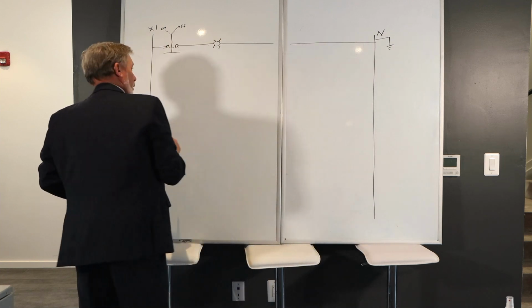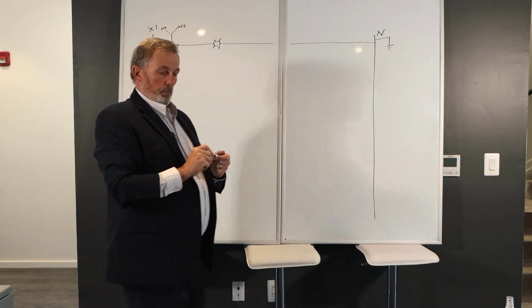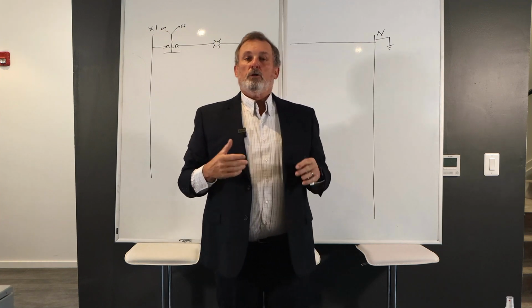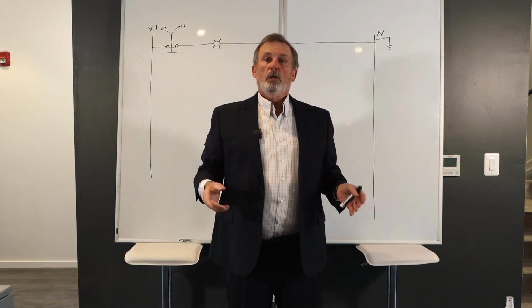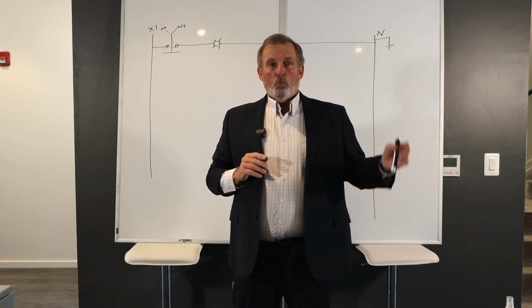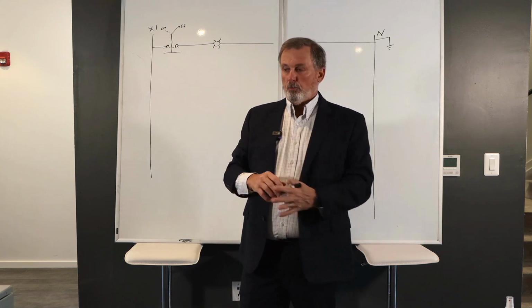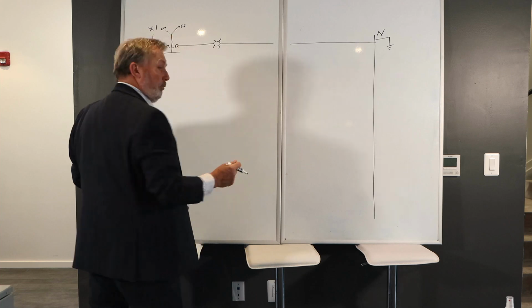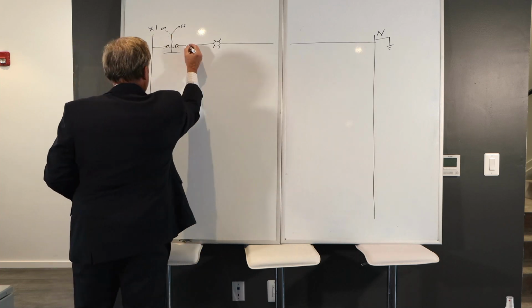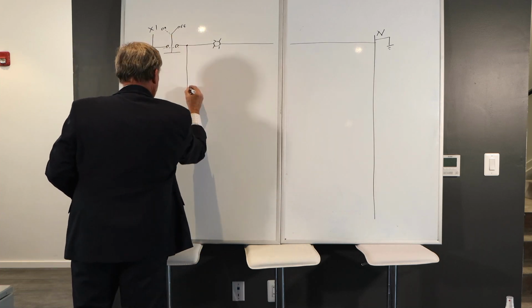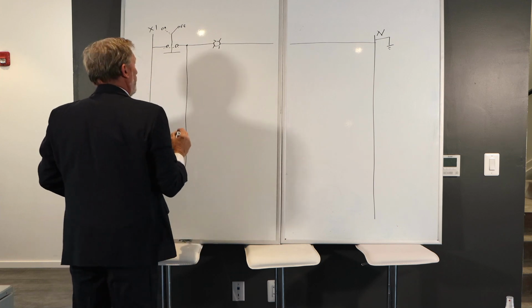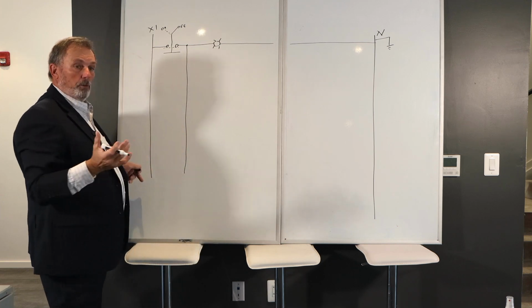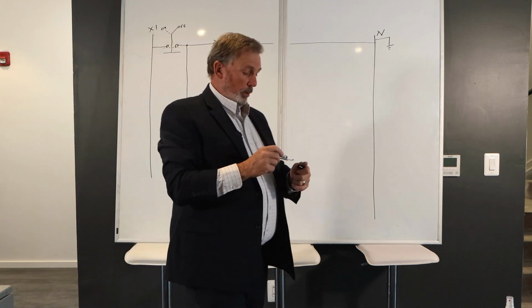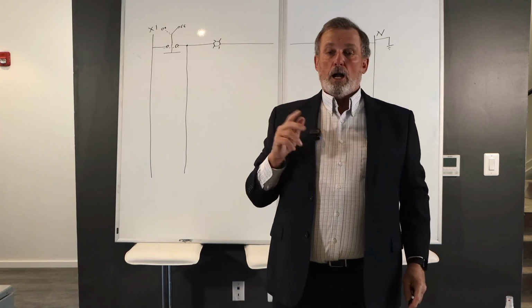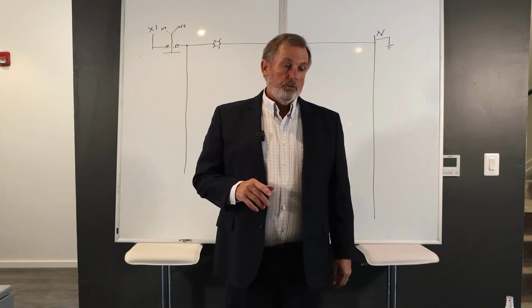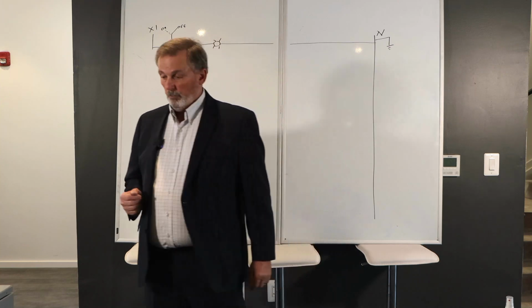Okay, very straightforward. Now, bear in mind that once that power comes on, that's going to be the power that's going to determine everything that we're going to do. So I'm going to take my number one rung and almost disregard it at this point. All of my control power now is going to come off of this point. This no longer becomes a viable source. I have the ability to switch my control power on and off. Let's take a look inside the cabinet and see what we've just drawn.